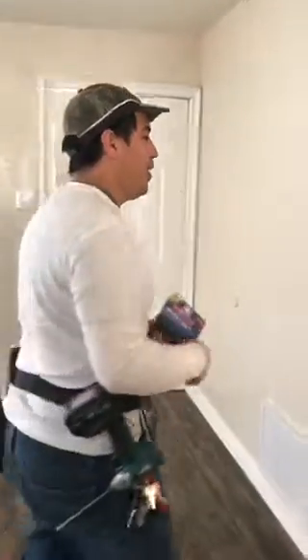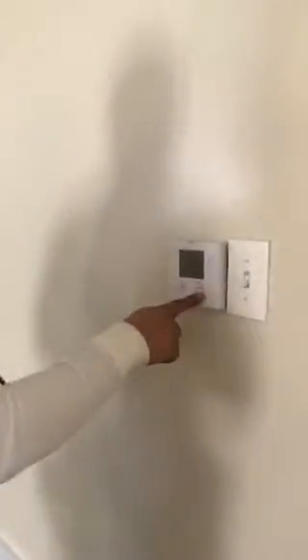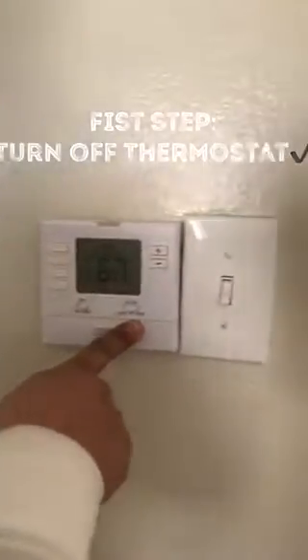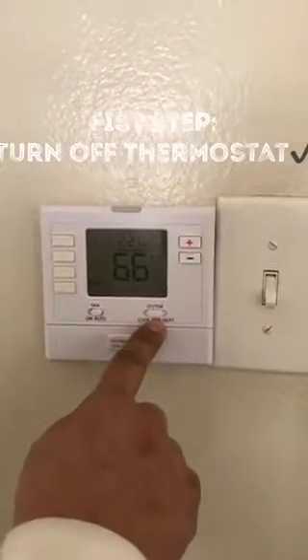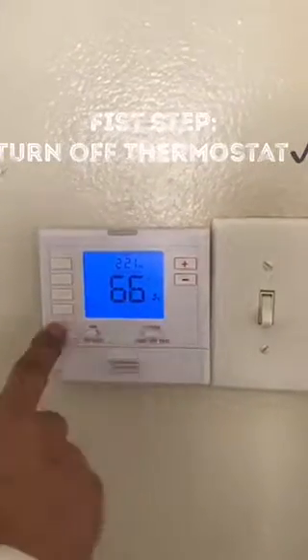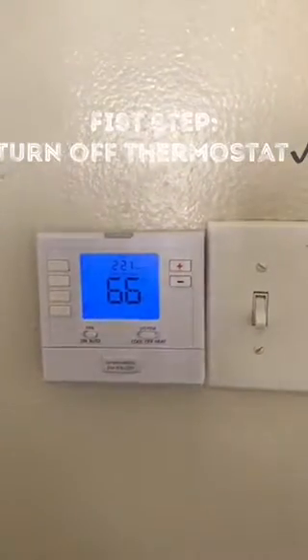Today we're gonna wire up a float switch to prevent water overflowing. The first step is making sure the unit is off at the thermostat so it's not sending any signal. Make sure it's at the off position and the fan is on auto, because if it's on, the fan is gonna come on — so just leave it at auto.